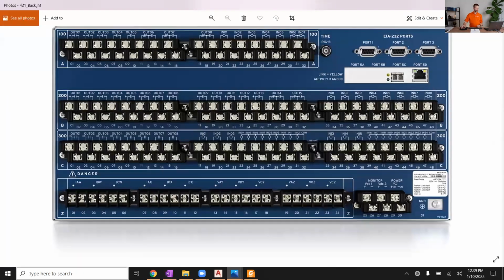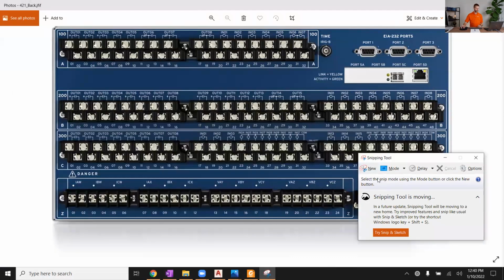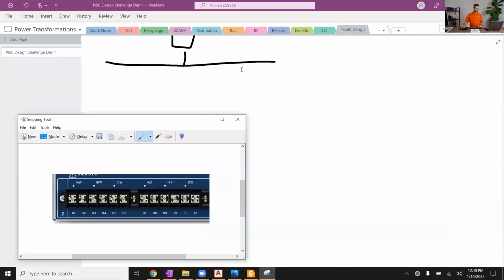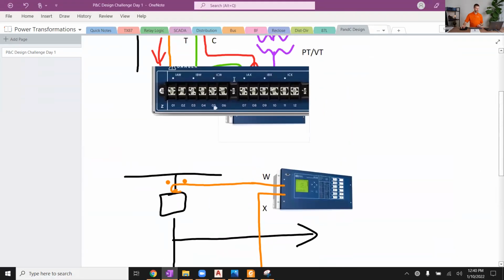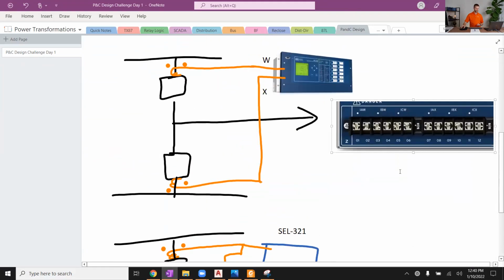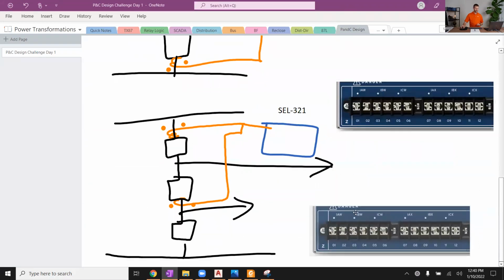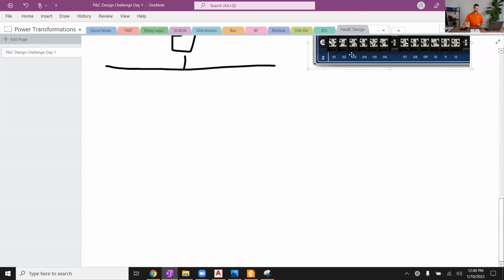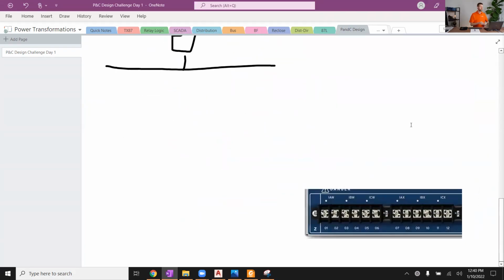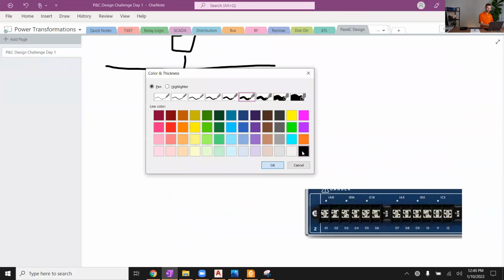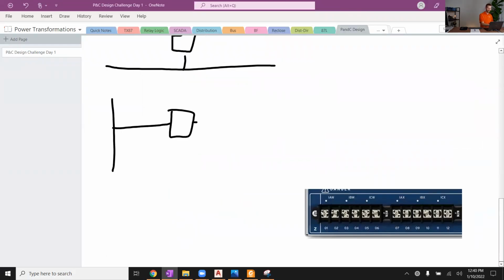I'm going to take our 421 back and I'm going to snip it here so that we've got our current terminals. And then let's paste that in here. Gotta figure out the OneNote interface, one second. There we go. And now let's draw our primary system, our one line once more, our bus, our breaker, and our line. We're just going to do a single breaker for simplifying this concept here. How would we wire? Actually, you know what? I meant to do a 3-line here. Let's try that again.